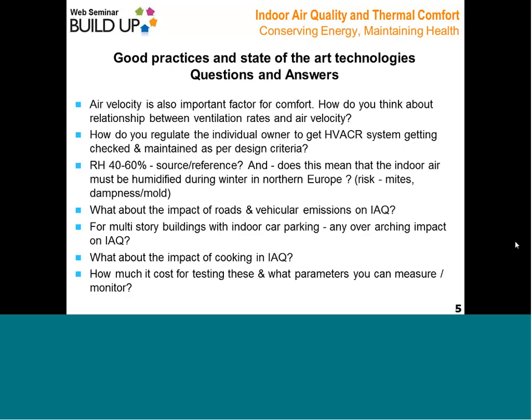In the European standard EN 15251, we also had this discussion. It says that normally, if you look at buildings used by people, it's not really necessary to humidify. This is for the whole of Europe, and it basically tells you that if you do have certain processes — like printing paper, or a museum where you want to protect the paintings — that could be a reason to humidify the air, but normally it's not necessary, also not in northern Europe.